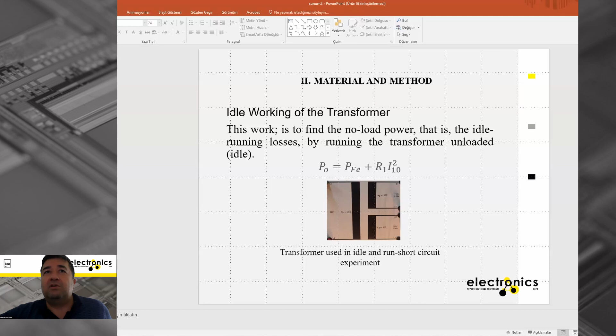This power is equal to iron losses, hysteresis and Foucault loss. There are two pictures here, the connection diagrams of the idle and short tests. In the idle test, it is considered the power is equal to iron losses, and iron losses depend on the frequency and voltage, because in the idle test there is not much current. So we can say the power loss is equal to iron losses.